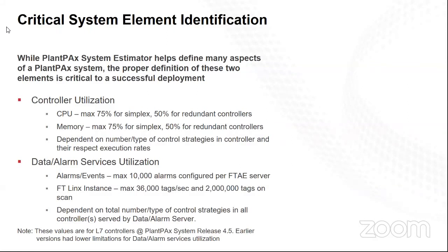And a big chunk of that is the processor we're using. We're still using the L7s for this. This is what everything is based on. So we know we have overhead that we have to account for with that particular CPU. And anybody who's done a redundant system in a PlantPAx system, this is always the gotcha. Don't run it above 50% on it.